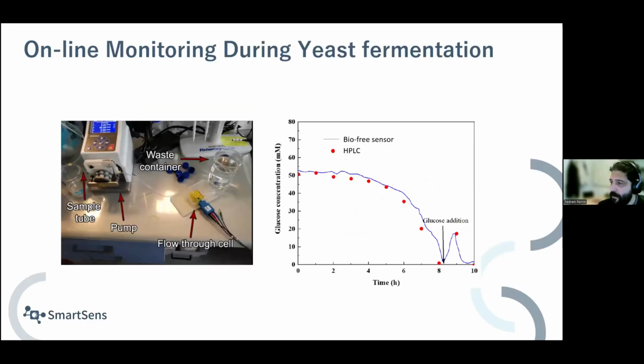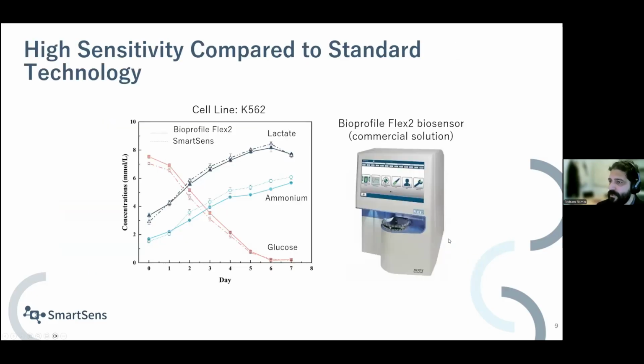Just to show you some of the results, this is for online measurements where we have integrated the sensors into a flow-through system to measure glucose in yeast fermentation. You can see during a 10 hours fermentation run, we can match those HPLC measurements, which are done every hour, with our real-time measurements from this online system with the platform. And then we also did a test to check the response of the sensor by spiking with glucose. Similar for offline testing with the mammalian cell cultivation, when we compared our sensor, SmartSens, with the Bioprofile Flex 2, which is also bio-free, we can see for all the analytes, lactate, ammonium, glucose, which are all important for CHO cells, for example, we also find a very good match.